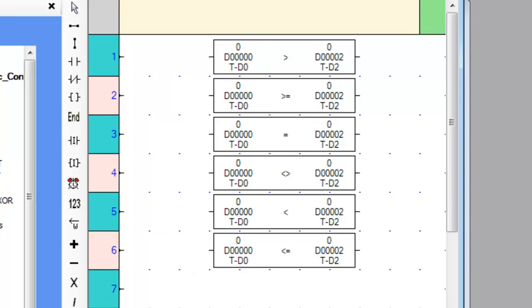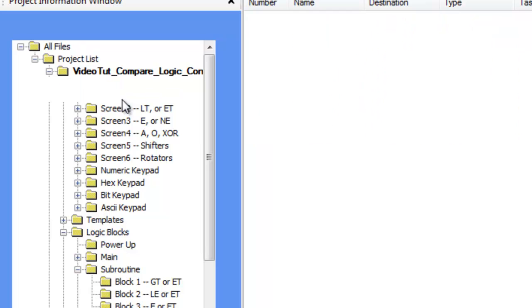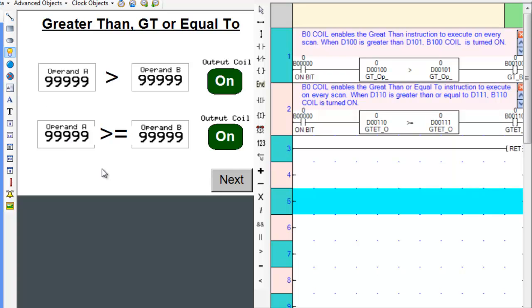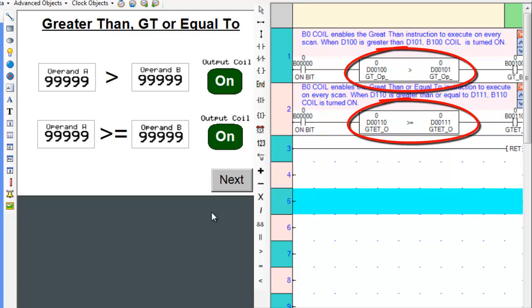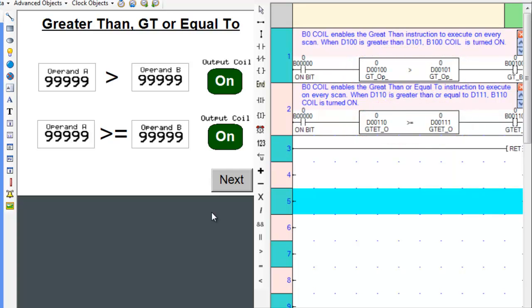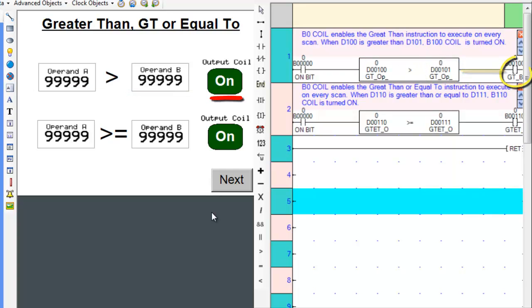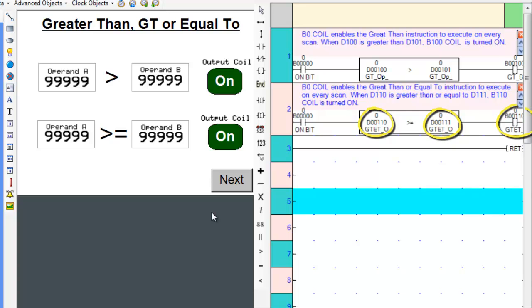Now that we know where all these instructions are, let's scroll over to screen one and observe how they work. Let's also place the appropriate ladder logic subroutine to the right of the screen. How the ladder instructions work is very simple. Both rungs in the logic block begin with a coil that is always turned on. The always-on coil enables the instruction to execute on every scan. As soon as operand A is greater than operand B, the output line is energized and the output coil is turned on. The same is true for the greater than or equal to instruction — when operand A is greater than or equal to operand B, the output coil is turned on.